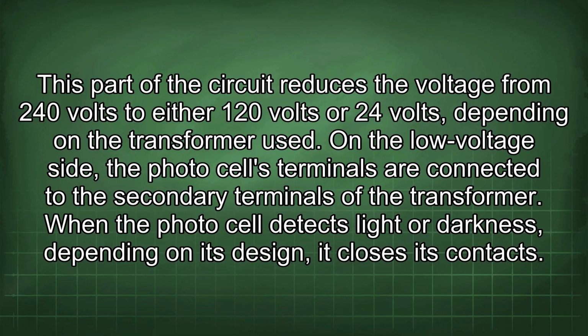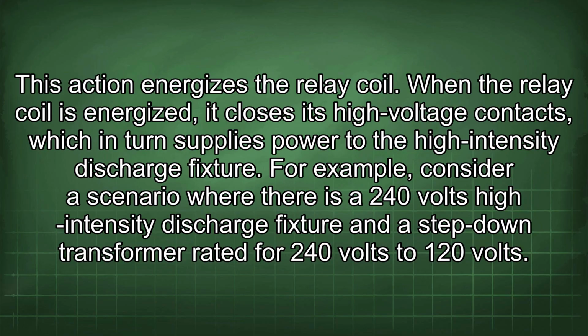When the photocell detects light or darkness, depending on its design, it closes its contacts. This action energizes the relay coil. When the relay coil is energized, it closes its high voltage contacts, which in turn supplies power to the high-intensity discharge fixture. For example, consider a scenario where there is a 240 volts high-intensity discharge fixture and a step-down transformer rated for 240 volts to 120 volts.